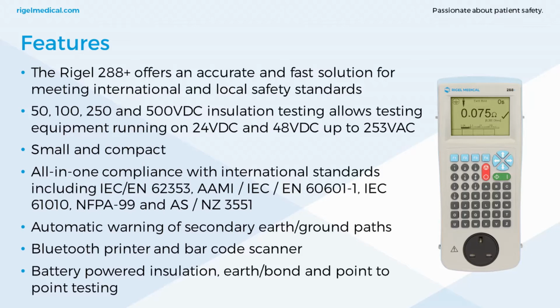So it's got all-in-one compliance with international standards including IEC 62353, AAMI or IEC EN 60601-1, IEC 61010, NFPA 99 and AS/NZS 3551. Different firmwares for this product, so if you're interested in having different configurations for your region, the 288 does have this capability. There's automatic warning of secondary earth ground paths, Bluetooth printer and barcode scanner available as an optional accessory, and we've got battery powered insulation, earth bond and point-to-point testing. I'll go into more detail on this in the demonstration video.